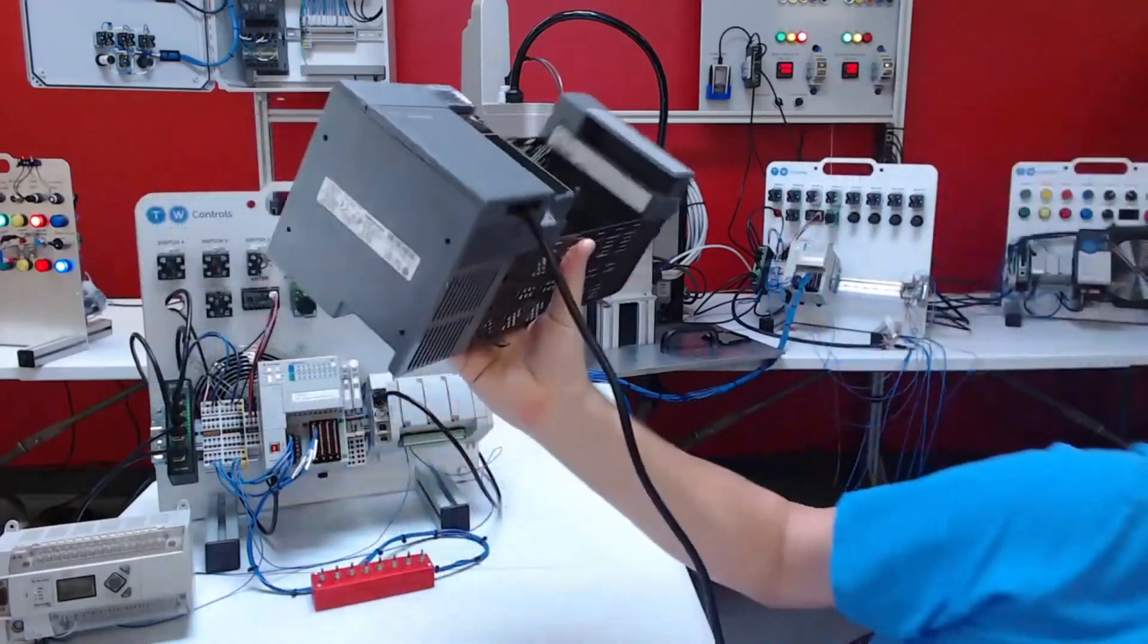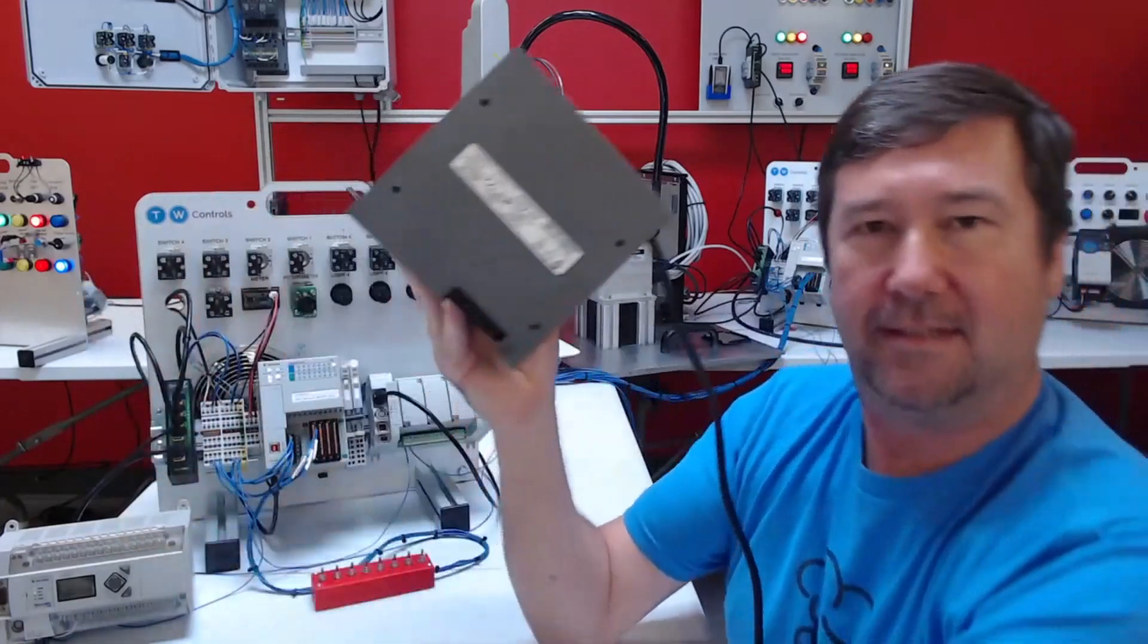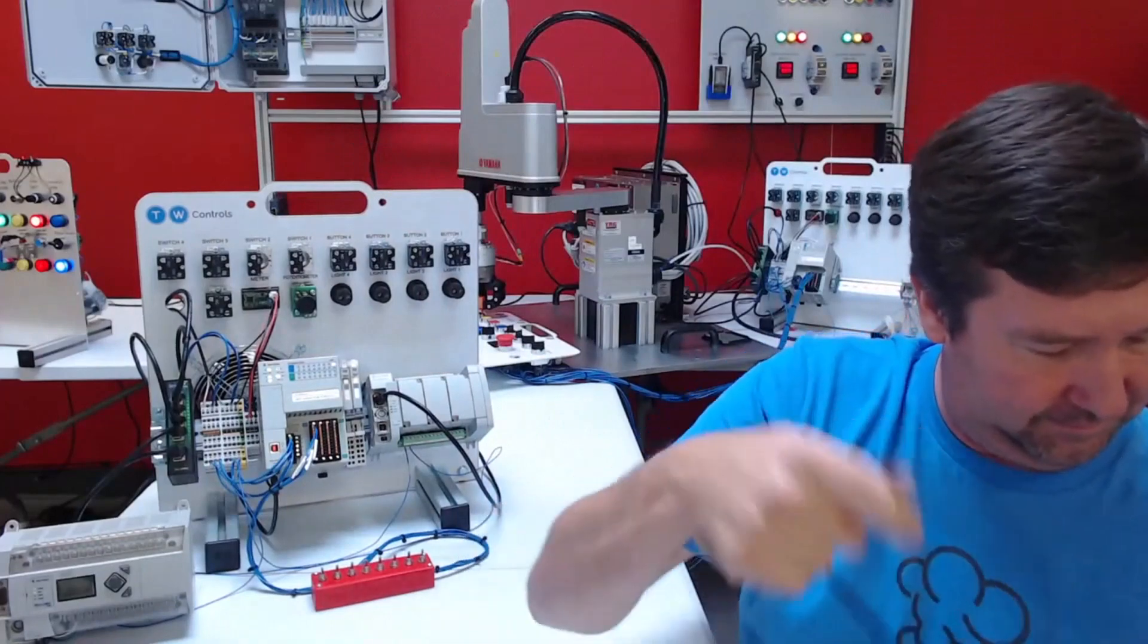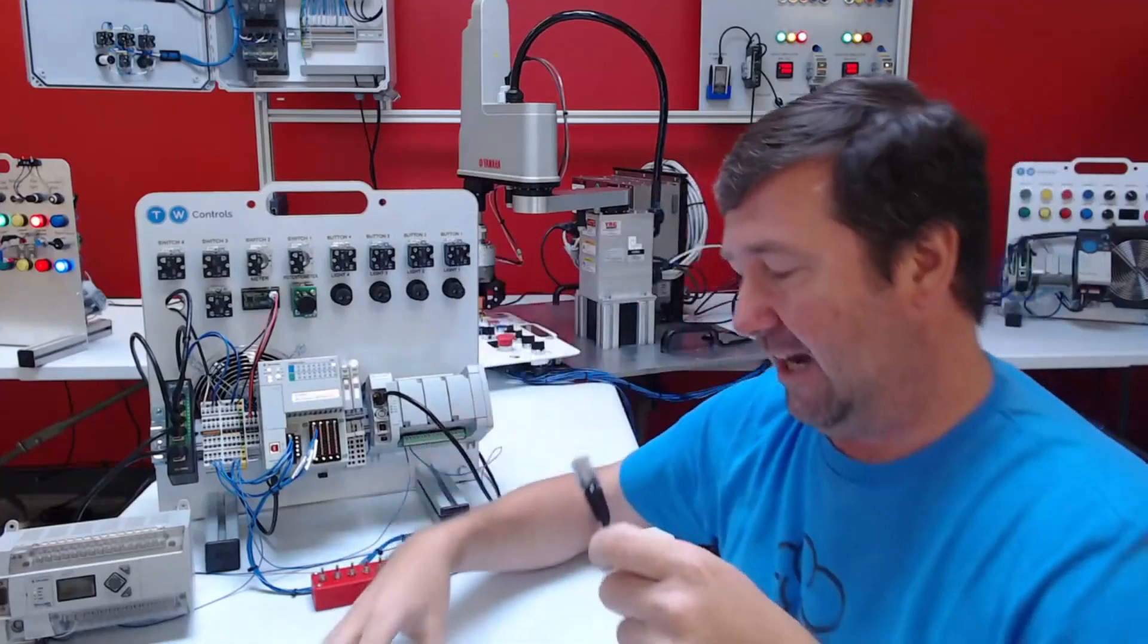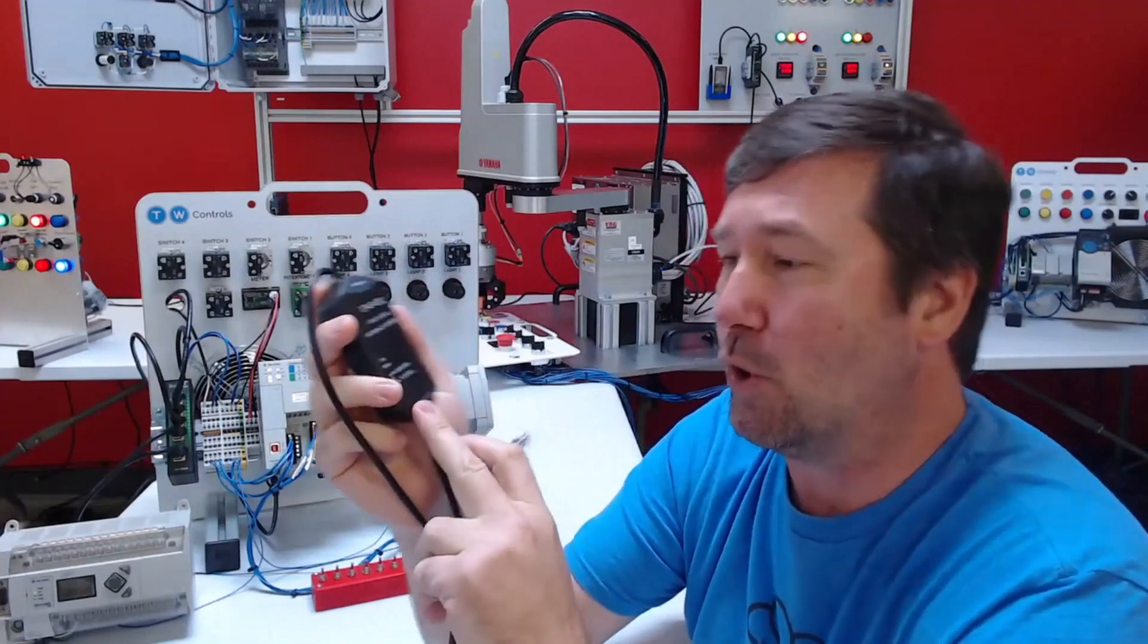For the top port we would use this 1747-UIC. Too many hands so I'm going to get this out of my hand. But it has a connector on it that looks just like ethernet but it's not. And this is not just a connector, this is actually a protocol converter also.